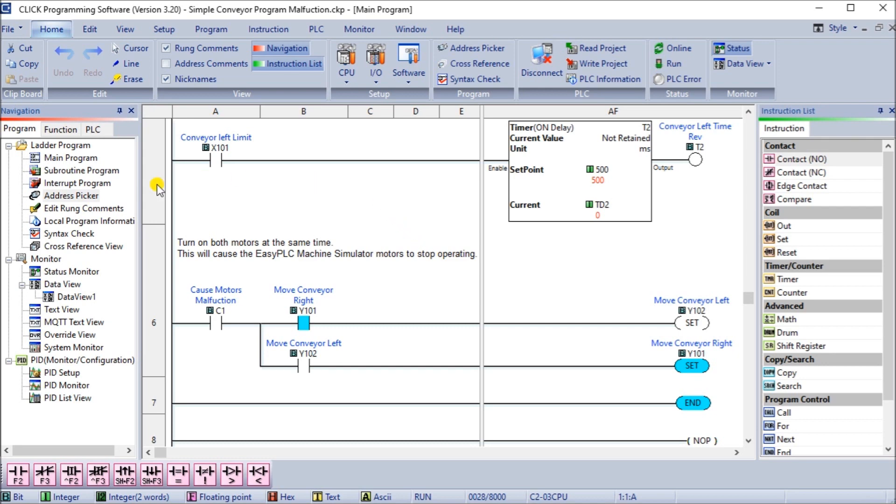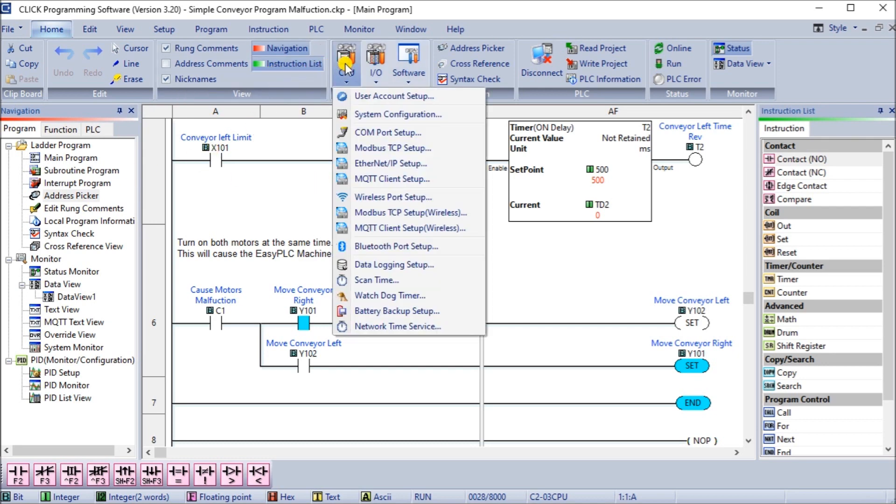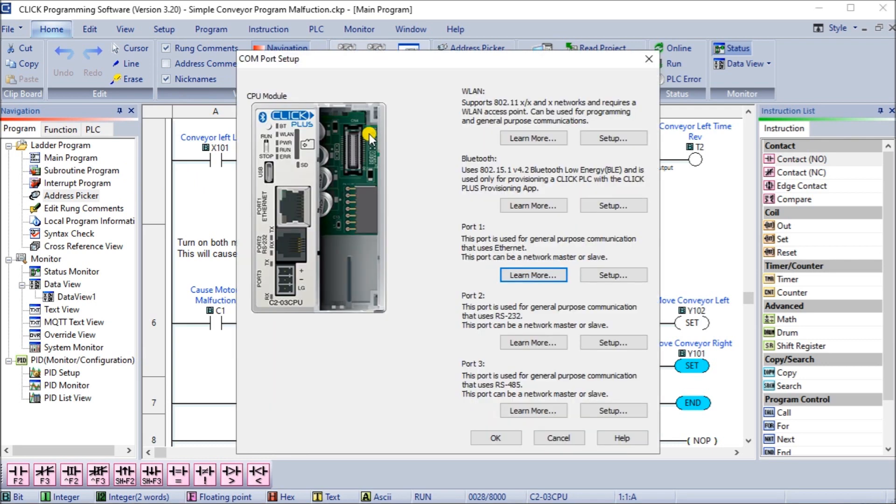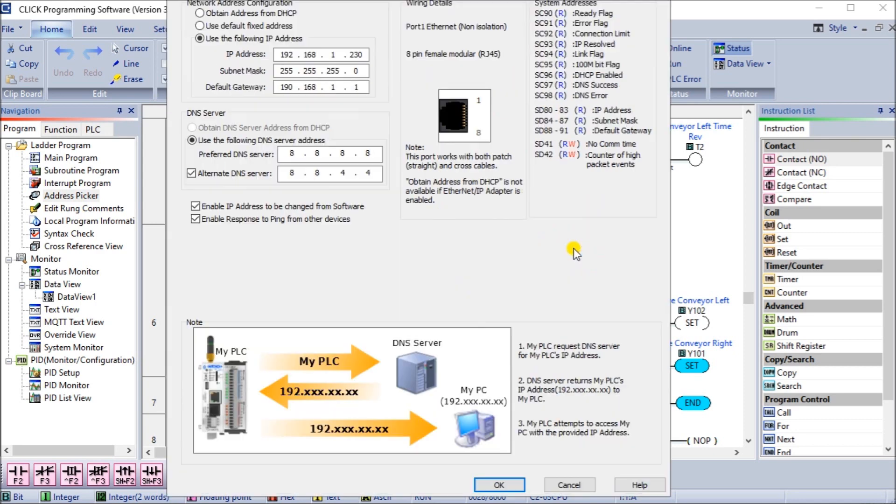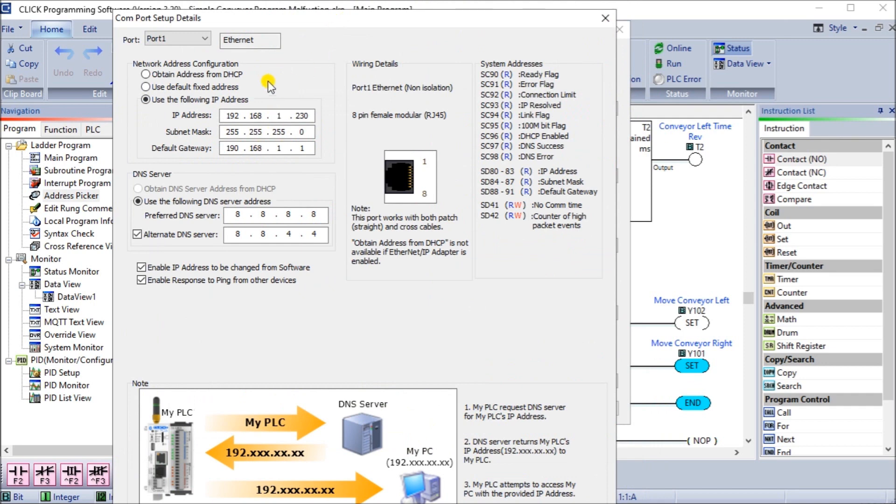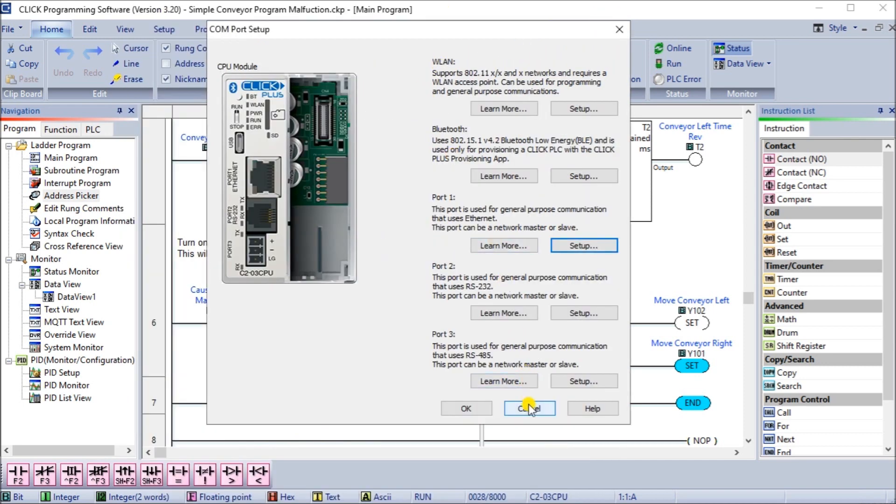Next, we'll take a look at our CPU and our COM port setup. Under our COM port setup, we want to look at port number one, which is our ethernet port. We'll look at setup. Under setup, you'll notice that we have a fixed IP address of 192.168.1.230. That is going to be our IP address that we must enter into our machine simulator in order to simulate this project. I'll close that down and hit okay. That's all set up. It's good to have a static IP address all the time in a PLC, so things that we want to communicate to will always know where they are.